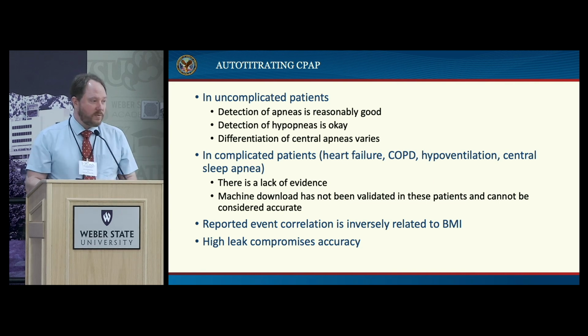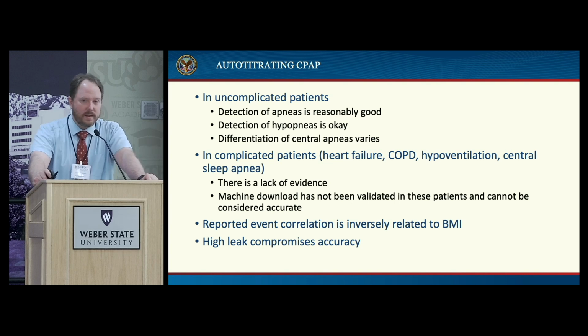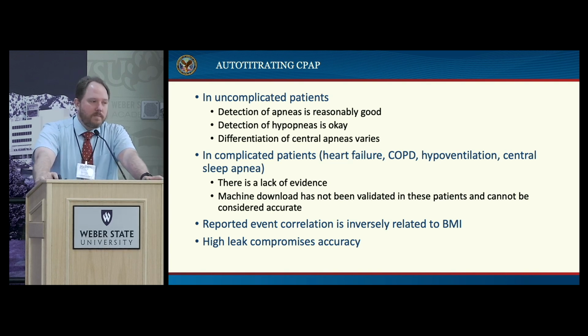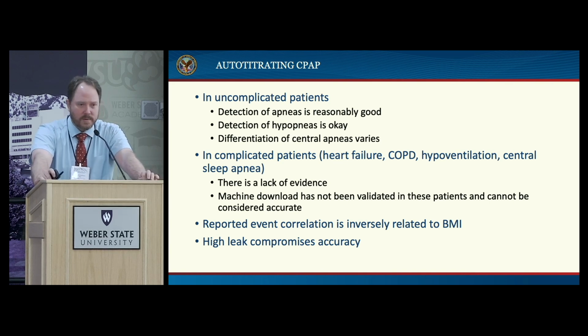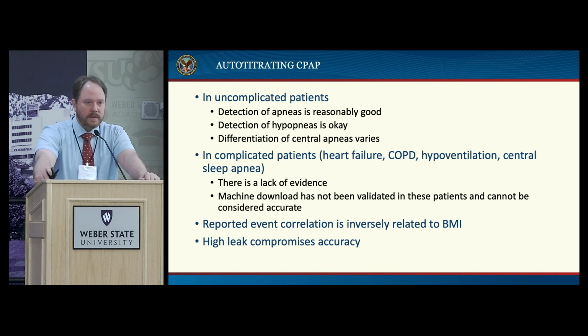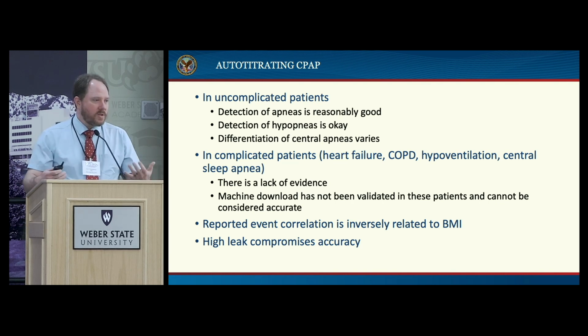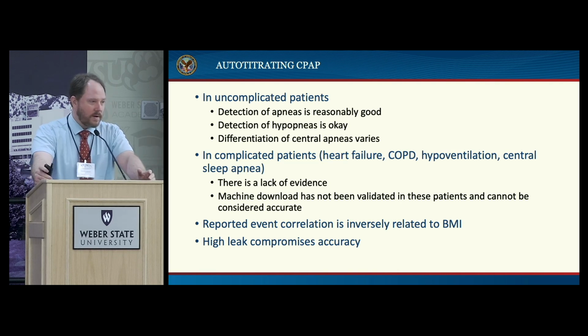They struggle to differentiate between the two types of apneas, central and obstructive, so I don't put a lot of weight in the distinction that the machine gives. They're really poor at detecting hypopneas. The R-squared value on the test was about 0.6. The reasons for this are pretty clear in that we're not measuring the same data, so we can't come to the same conclusions.